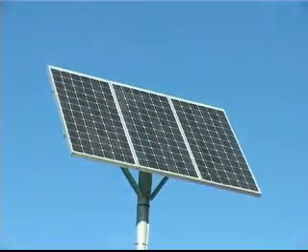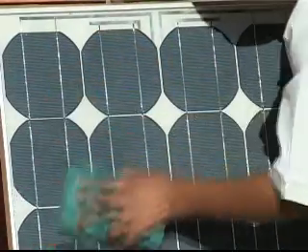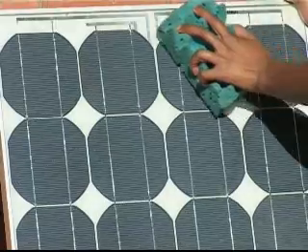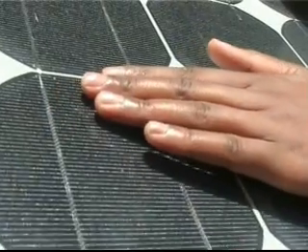For the system to function optimally, unobstructed sunlight is of great importance. Therefore, panels should be placed in full sunshine and washed down when necessary. Clean the panels with cold water only, because soap and detergents will degrade the sealing material. Use only clean water and a sponge and always clean the panel when the sun is not very hot. This avoids the so-called hot spots forming on the glass panel. Dry the panels after cleaning. Visually inspect the solar panels for damage.